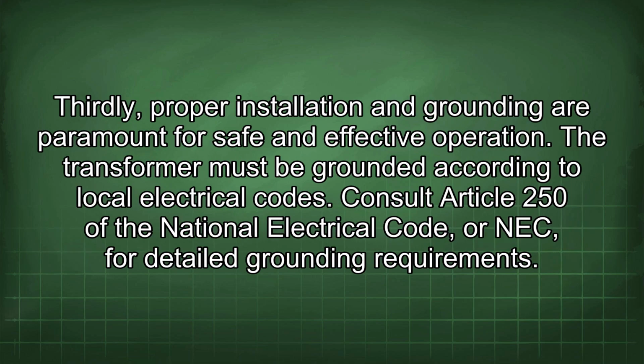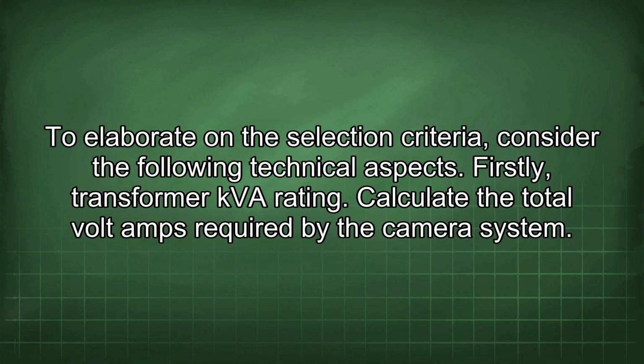Thirdly, proper installation and grounding are paramount for safe and effective operation. The transformer must be grounded according to local electrical codes. Consult Article 250 of the National Electrical Code, or NEC, for detailed grounding requirements. To elaborate on the selection criteria, consider the following technical aspects.